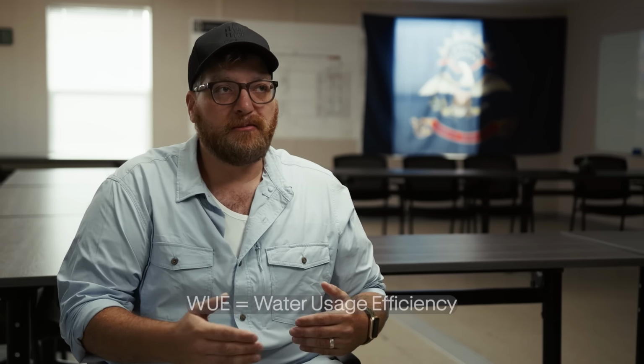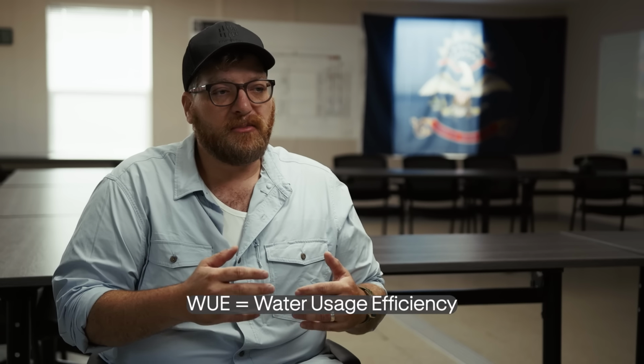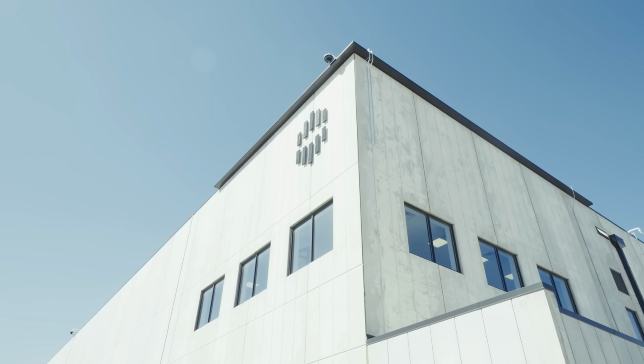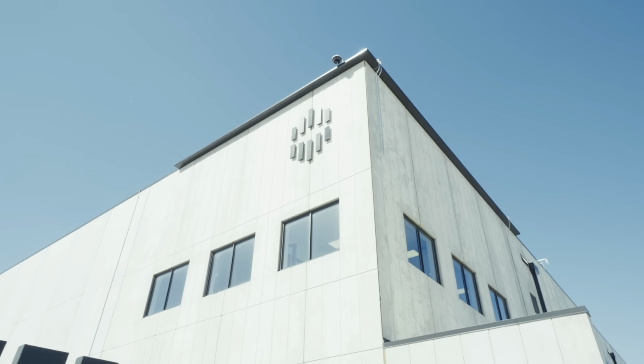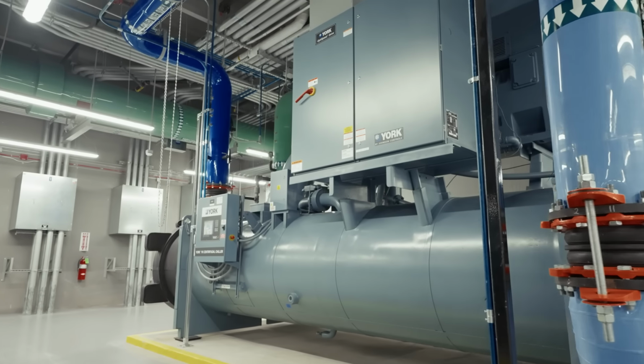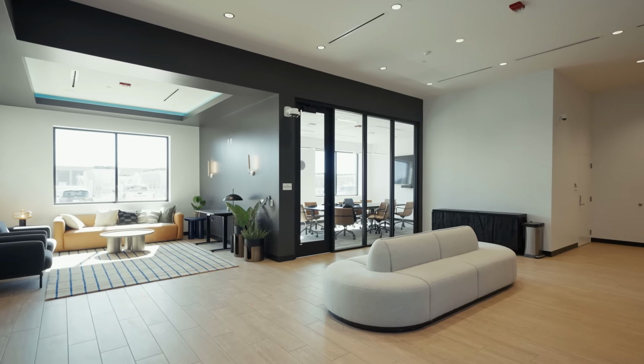Moving forward, as we're looking at WUE and trying to limit as much impact as we can on the domestic water system in whatever community we get set up in, we're installing water meters that communicate how much is being pulled into the building through the main line domestic water feed. Then we'll have meters on all of our process equipment. We're essentially taking total water fed into the building, less humidifiers, less makeup water to the loops. What you're left with is what's used in restrooms, sinks, and water fountains. So that number from our process is what we actually use to do what we're doing in a data center.